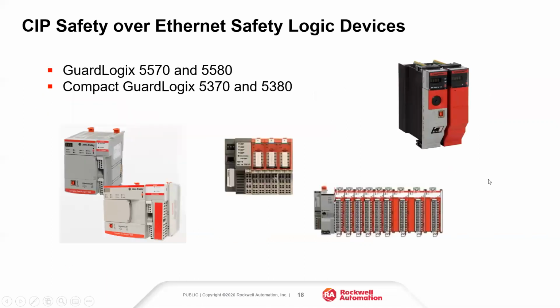All right, so then we're going to move on to what does it look like on the logic side. Hopefully most of you are familiar with these, but we have both the GuardLogix 5570 and 5580 controllers for the logic side, as well as the Compact GuardLogix 5370 and the 5380 that can be used. So like Mark was mentioning earlier, CIP safety over Ethernet requires the use of a safety controller, because everything's going to be on a network and will be brought back into the controller.